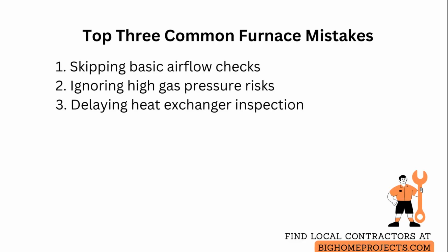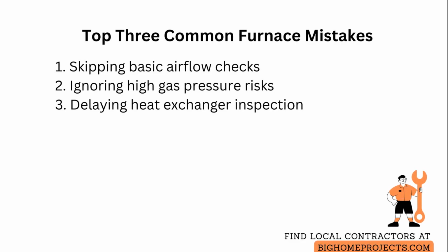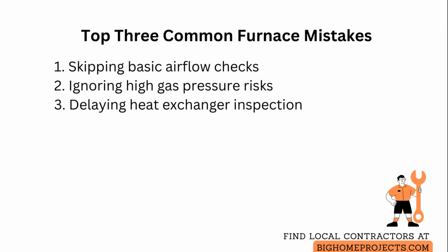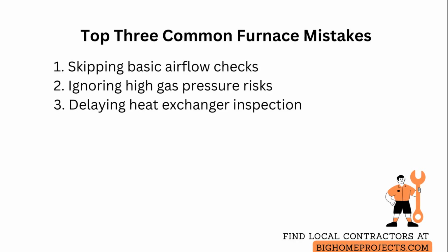Most people miss basic airflow checks and replace controls without fixing the root problem, so always verify filters, vents, and blower function before swapping parts.